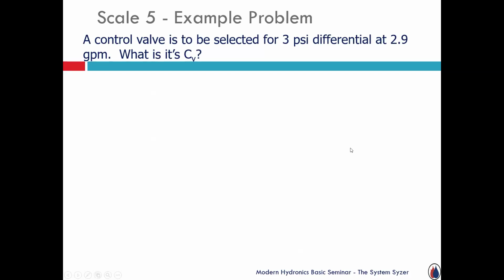So a real quick example of how you might state it or might use it. A control valve is to be selected to cause a 3 psi differential. Say it's a control valve on a chilled water coil. And the chilled water coil is supposed to, now we're getting, again, back to the weeds, 2.9 GPM through that coil. So the control valve is selected to cause a 3 pound pressure drop when there's 2.9 gallons a minute going through that valve. So you work backwards and say, hey, what's the CV rating of the valve that I should select so that when it sees that condition of 2.9, it will create that 3 pound pressure drop I'm chasing after to have maybe some good control valve authority.